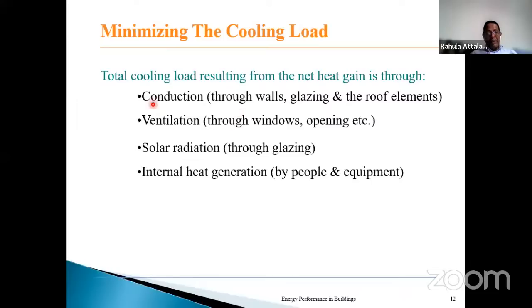Conduction will depend on the material of the wall and the windows. Ventilation will depend on the size of the opening. Solar radiation will depend on the material properties of the window, the transparent material. And internal heat generation will depend on the efficiencies of the equipment and the number of people. Each one of us, depending on our activity, would release at least 100 to 120, 150 watts. If it's a gymnasium, etc., maybe even more than that. Imagine if you have 10 people, so you have 1 kilowatt inside the building. It's like burning a 1 kilowatt lamp.